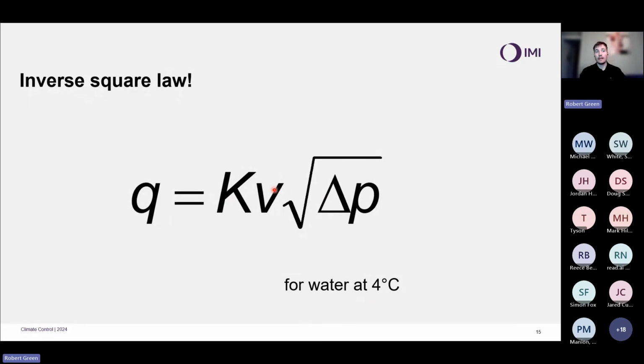And the simple way we can look at this kV as a function, in essence, if we break it down, is that it is equivalent to the area inside that device. So with a valve, the smaller the area is, the lower the capacity for flow is. The smaller the restriction, the lower the capacity for flow, which, if you think about it, makes sense. I would need a higher differential pressure across a piece of equipment if it had a smaller opening than a larger opening piece of equipment.